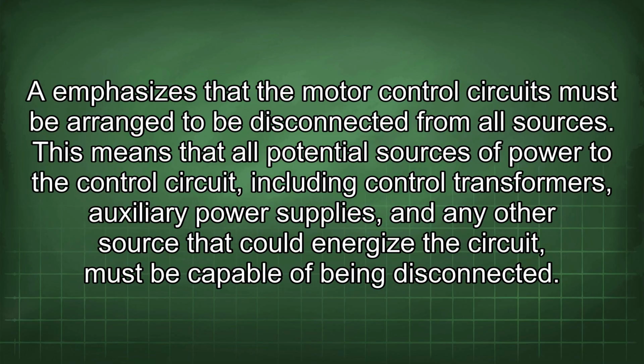430.74 emphasizes that the motor control circuits must be arranged to be disconnected from all sources. This means that all potential sources of power to the control circuit, including control transformers, auxiliary power supplies, and any other source that could energize the circuit, must be capable of being disconnected.